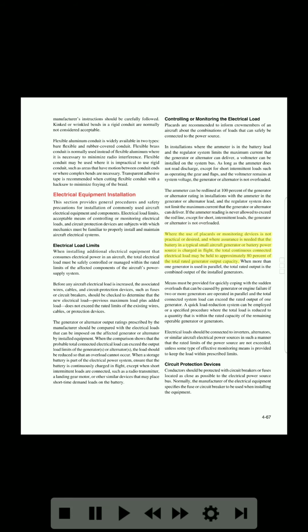Where the use of placards or monitoring devices is not practical or desired, and where assurance is needed that the battery in a typical small aircraft generator or battery power source is charged in flight, the total continuous connected electrical load may be held to approximately 80% of the total rated generator output capacity. When more than one generator is used in parallel, the total rated output is the combined output of the installed generators. Means must be provided for quickly coping with the sudden overloads that can be caused by generator or engine failure.